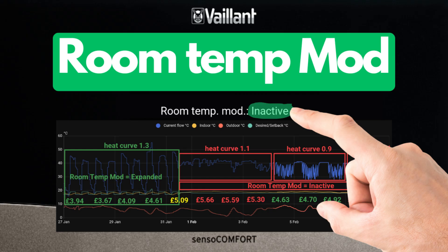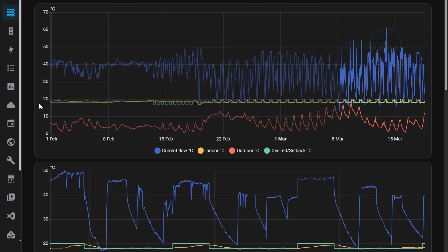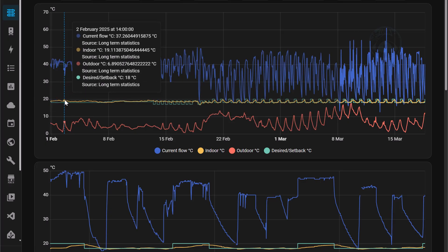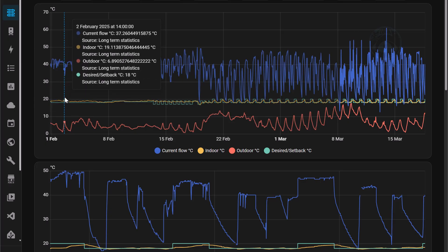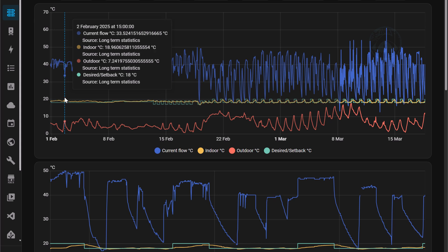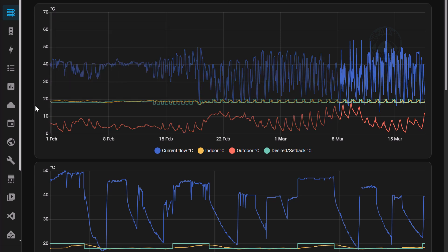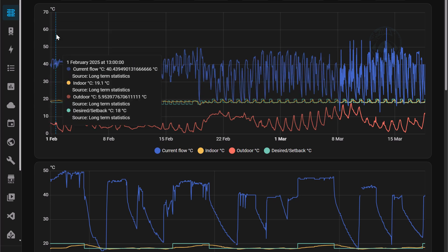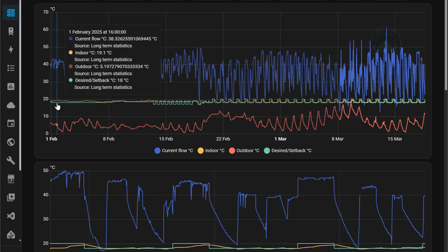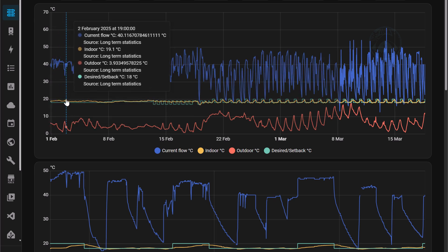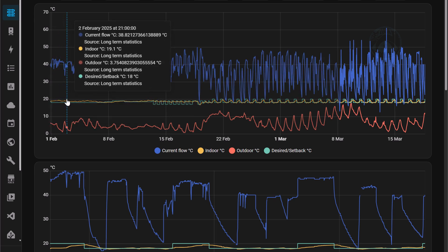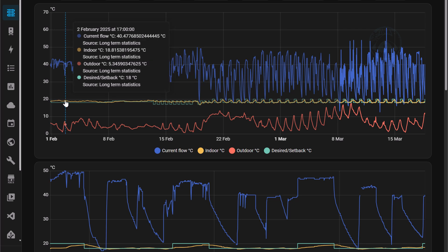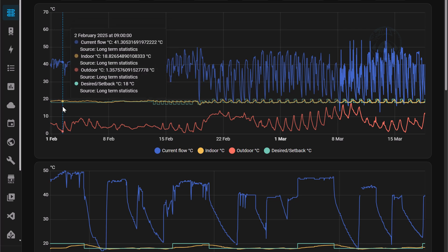Basically, I'd been testing in the late part of January room temperature mod equals expanded and I had a heat curve of 1.3, and then I wasn't really sure if expanded was the right setting to be on. But prior to that I had been testing all sorts of options and heat curves and different timers, so I wanted a more consistent static setup and that's why I went with expanded with a heat curve of 1.3.